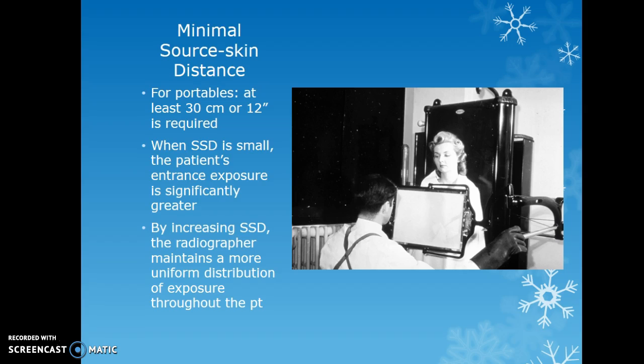For source-to-skin distance on portables, at least 30 centimeters or 12 inches is required. The main concern arises in the NICU with premature infants — if they are in a crib with a fixed top, you may need to move them to a Mayo stand or different crib to achieve sufficient distance, because you cannot be closer than 12 inches.